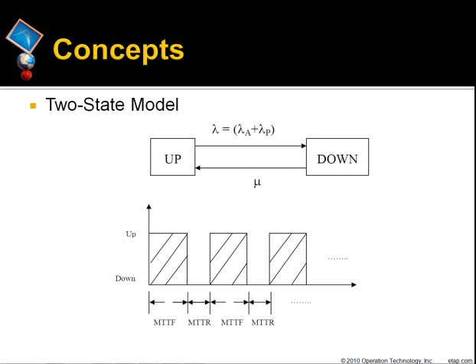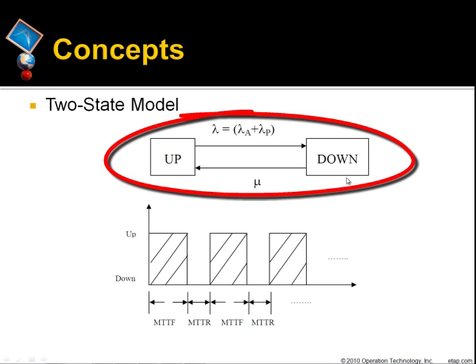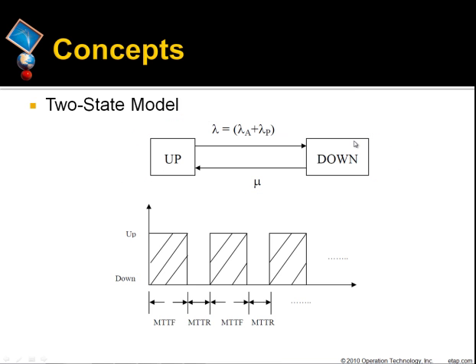We would like to review some basic concepts of reliability calculations. Components are represented by a two-state up-down model, which is used for the operation-repair cycle of components such as lines, cables, transformers, breakers, fuses, switches, loads, and bus bars. Active failure rate, number of failures per year, represented by lambda A, represents the failure that causes the operation of the primary protection zone around the failed component and can therefore cause the removal of other healthy components.